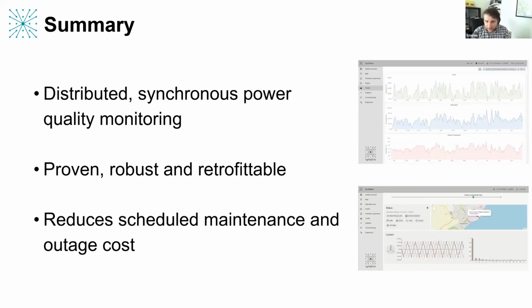Just to go over that again, this is a solution for distributed sensing, which is synchronous, so that we know the exact timestamp of every sample that we take, and we organize it so all of the sensors are sampled at the same time. So we completely eliminate that issue of needing to synchronize multiple different power quality meters. It's all taken care of, built into the platform. We've already deployed this in a number of locations, including offshore wind, and we know it works, and it's robust, particularly because it doesn't need data communications to be provisioned or other complications like GPS clocks, and it can be retrofitted to existing installations.